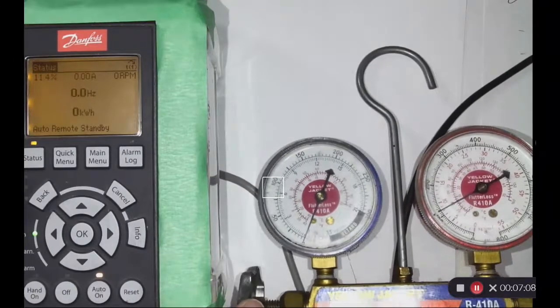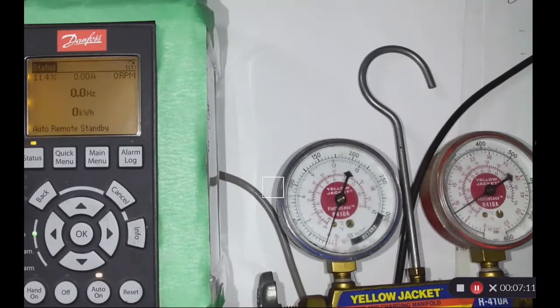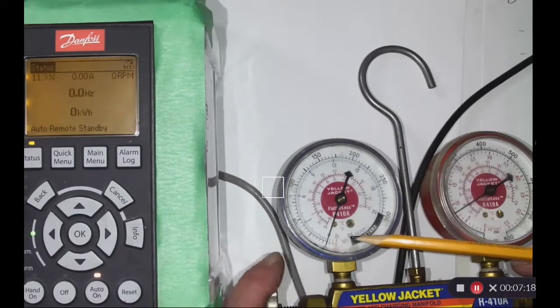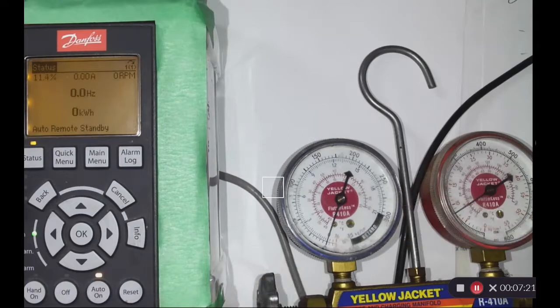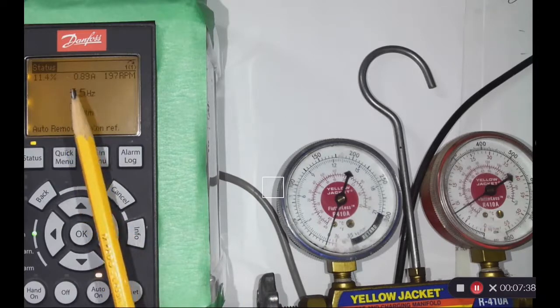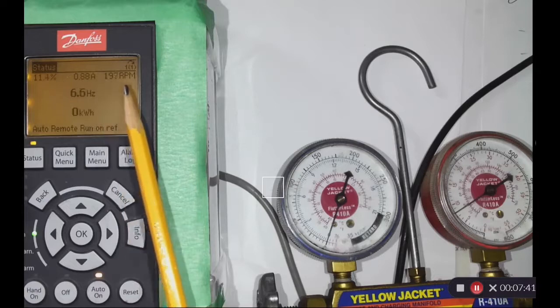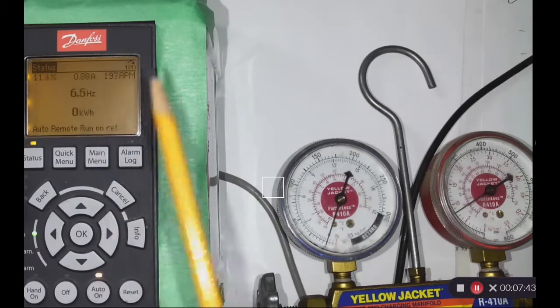These are 410 gauges, so you don't move the needle very much with our 410 gauges. I should use my R12 gauges. I have some kicking around here. And you can see there's no pressure on the transducer, and this tap on the left is open. So what I'm going to do is hit the forward reverse digital input to on, and now you can hear the drive is running, take my word for it, and it's at 197 RPM up here at 6.6 hertz, and it scales it to that.